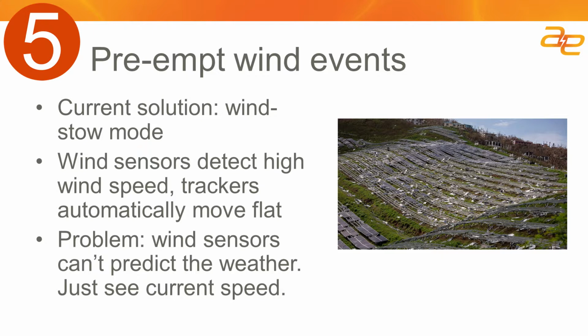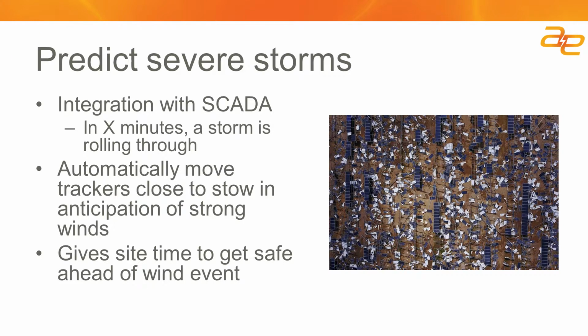The problem with that system is that it's not predictive. The wind sensors get the wind speed as it exists at that moment and can't really predict when there's a wind event coming, whereas with something like a Met station or an RSS feed, the SCADA systems often know what the upcoming weather is for a site, and they can anticipate that wind is coming in an hour, so you can start to move the modules to a safer stow position as the wind starts to build.